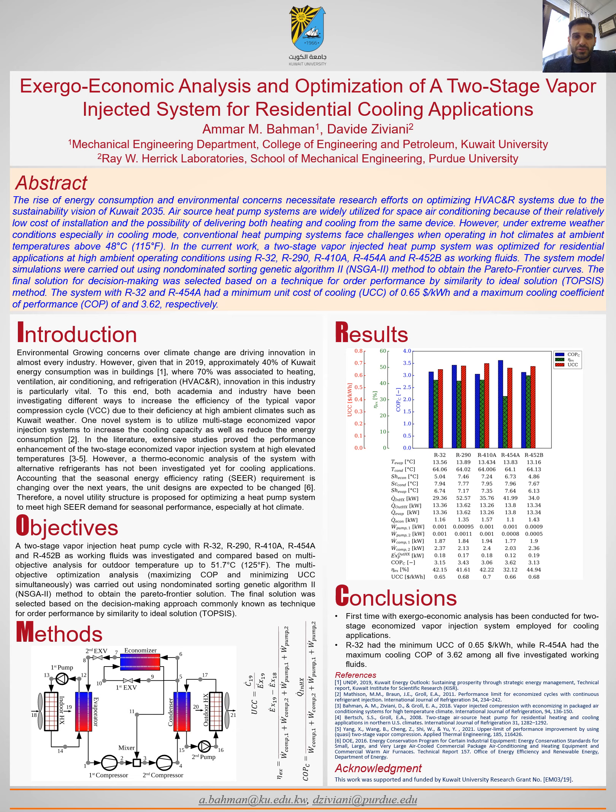What motivates us to conduct this research is due to the growing concerns about the global environment and energy consumption, given that about 40% of Kuwait's energy consumption is in buildings and 70% of this energy is consumed by air conditioning systems. We found that novel cycles such as vapor injection and economization can indeed improve the overall performance, because injecting cold refrigerant into the compressor shell can reduce the heat generated during the compression process and therefore reduce the power consumption.